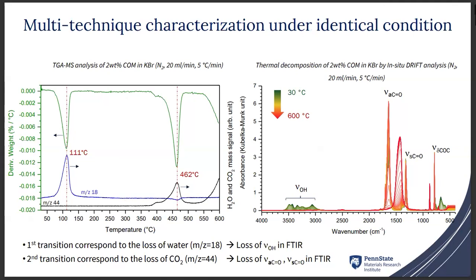That's a good question. Thank you for the question. So first of all, this temperature calibration is proper for this particular rate or particular ramp of temperature. And if you change the temperature ramp, then you need to do another calibration to make sure that the temperature is stable. Second of all, this is the main difference between thermal analysis methods such as TGA and DSC, where the ramp is extremely fast, and spectroscopic or diffraction methods, where the acquisition of the data takes time, so the ramp needs to be slower. And that's why I did this comparison with the TGA under the same condition for the FTIR, because I had to reduce the ramp to 5 degrees per minute in order to make sure that I have identical data.